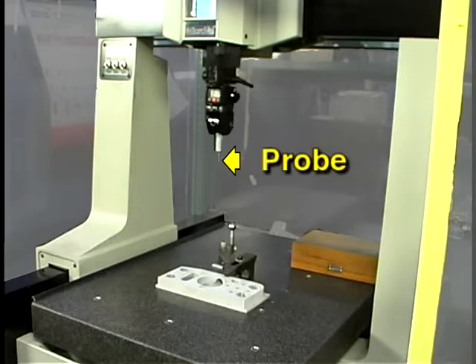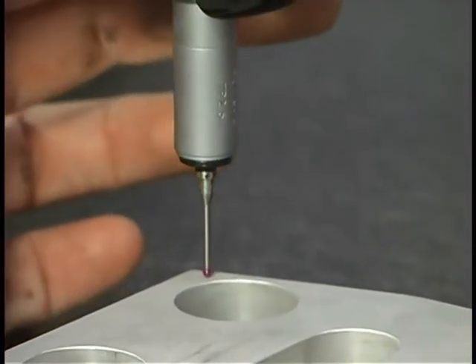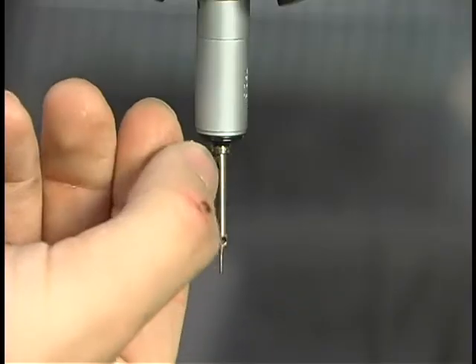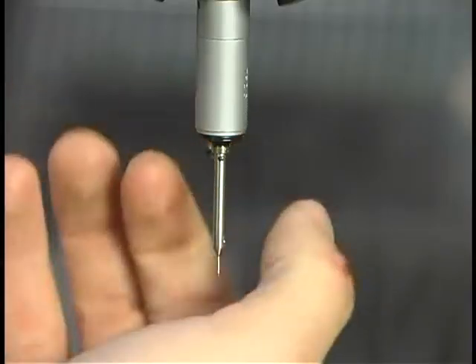This is the probe. The probe and probe tip can be adjusted to measure various part features. The probe tip can be replaced if a different diameter tip is required for the feature being measured or if a tip becomes damaged.